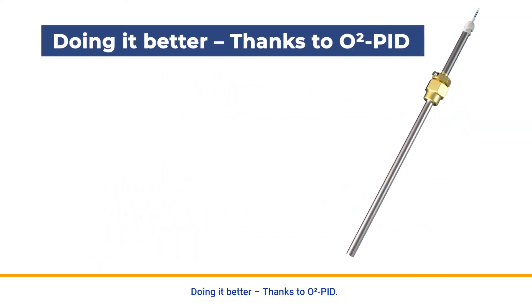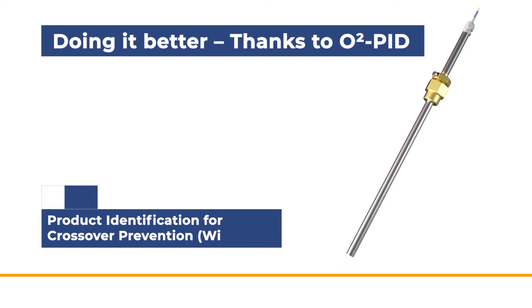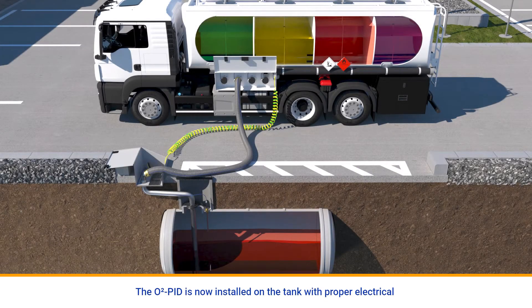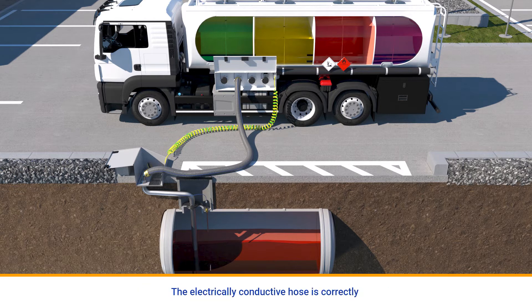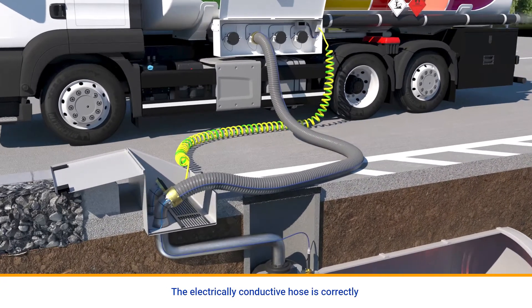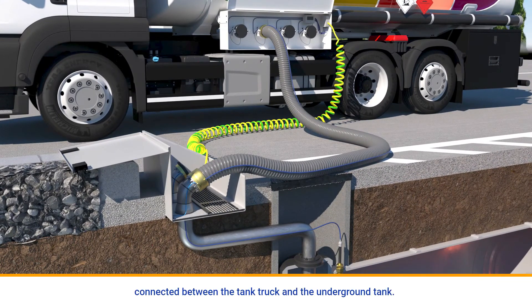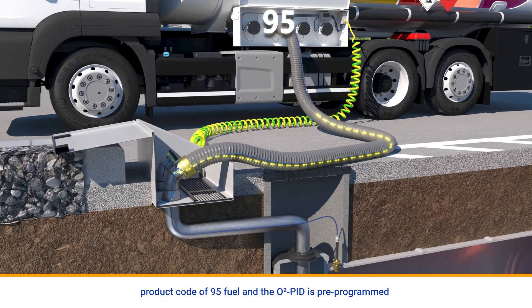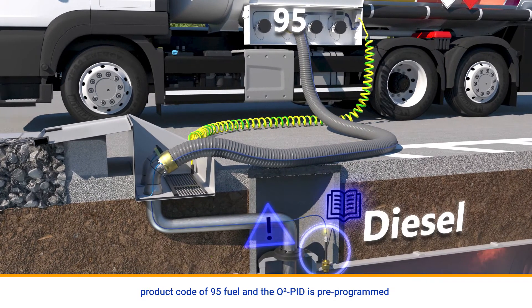Doing it better — thanks to O2PID. Scenario 2: Product identification for crossover prevention with O2PID. The O2PID is now installed on the tank with proper electrical connections to the delivery inlet of the underground tank filled with diesel. The electrically conductive hose is correctly connected between the tank truck and the underground tank. The truck amplifier is pre-programmed with the electrical product code of 95 fuel, and the O2PID is pre-programmed with the electrical product code of diesel.